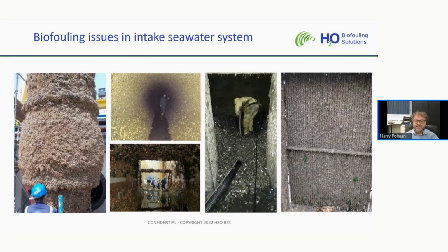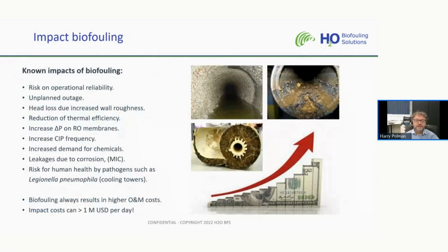Fouling needs cleaning. So once your system is fouled, you need to clean it. And often it needs physical cleaning, like you see in some pictures, by people who have to dig out the fouling organisms from the system. The impact of biofouling can be quite severe. Biofouling can result directly in an unplanned outage of the system. Usually that's caused by head loss in an intake pipe, which increases wall roughness, which results in head loss in the intake pump basin, or blockage of your condenser heat exchanger.